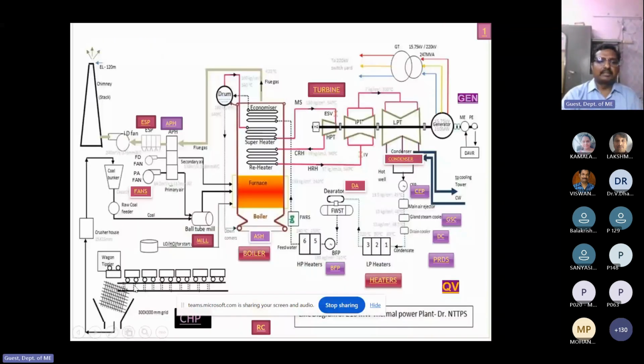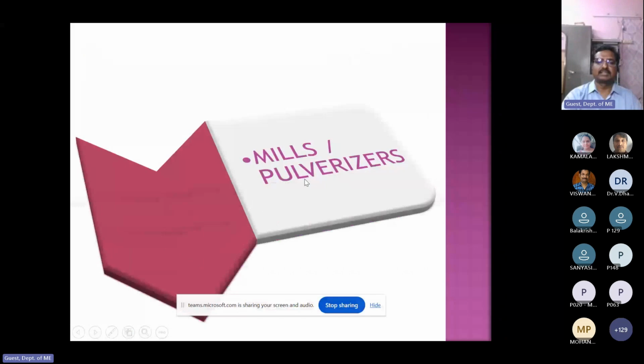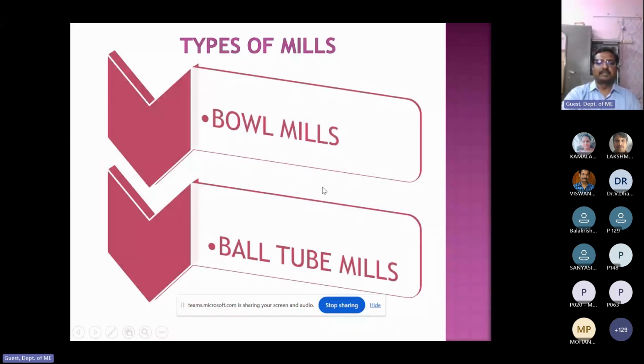So after the coal handling plant, the coal directly comes up to the mills. This is the mills or pulverizer. Generally, pulverizer mills are of two types: ball mills or bowl mills. In 210 megawatts here in this Ibrahimpatnam plant, we are using both types of mills. Unit 1 and 2 are using ball mill. Unit 6 is using bowl mill.